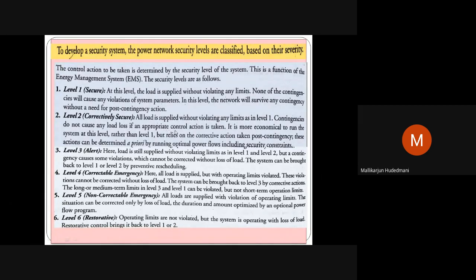If an appropriate control action is taken, it is more economical to run the system at this level rather than level 1. But it relies on corrective action being taken post contingency. These actions can be determined a priori. Well, before it occurs, we have to anticipate and keep remedies ready. That's called a priori. A priori refers to a mechanism or schedule kept ready for a certain problem. What is the cause? What is the remedy for that? That measure is called a priori, determined by running optimal power flow including security constraints.